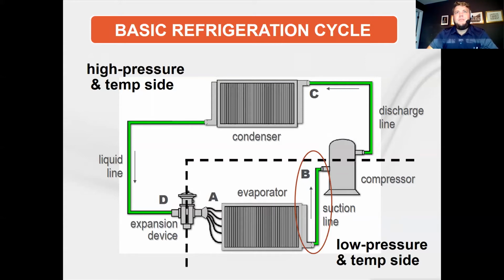If we start here at our evaporator, the basic refrigeration cycle that's most commonly used in air conditioning applications consists of 4 main components. We have the evaporator, compressor, condenser, expansion device, and a bunch of different things in between, including controls, but we'll discuss the operation of these real quick from the basics. The evaporator is most often a fin and tube style coil that is paired with an air handler, some air moving unit or device, and it extracts heat from the space that's trying to be conditioned, and it absorbs it and evaporates the refrigerant that is inside of the system.